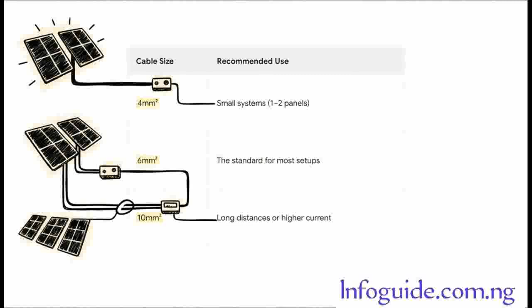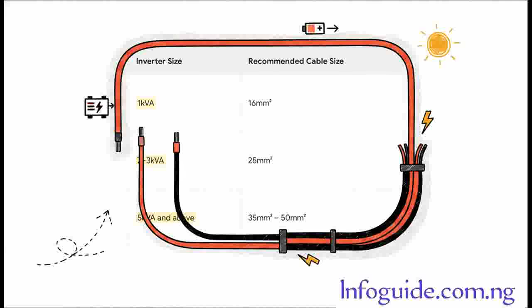Now for the heavy hitters, the battery cables. This is the one place where you absolutely cannot afford to cut corners. The cable size here is tied directly to your inverter's power. Even a small 1 kVA inverter needs a hefty 16mm squared cable. Jump up to a common 3 kVA inverter, and you're already looking at 25mm squared. For any serious 5 kVA setup or larger, you're in the 35 to 50mm squared range. These cables are thick for a very good reason.